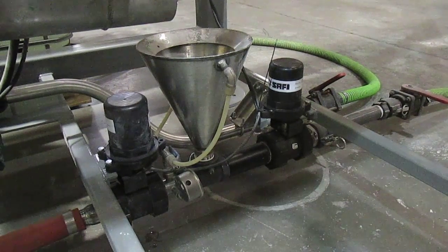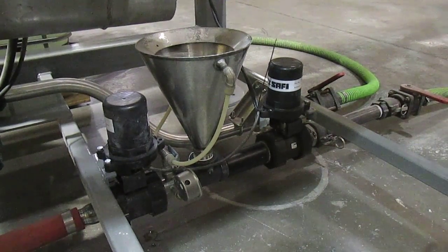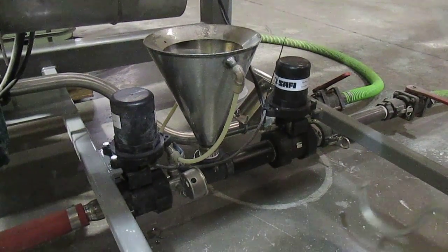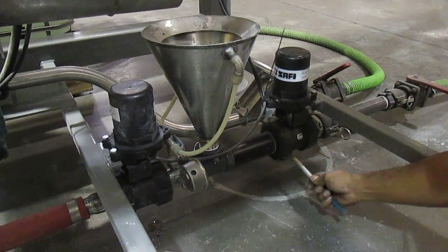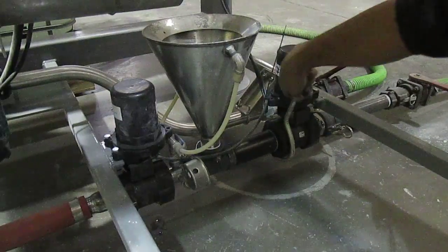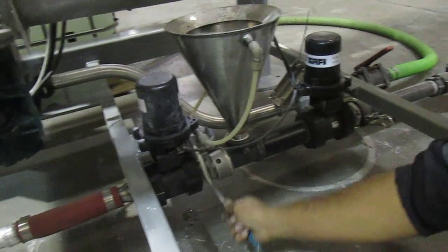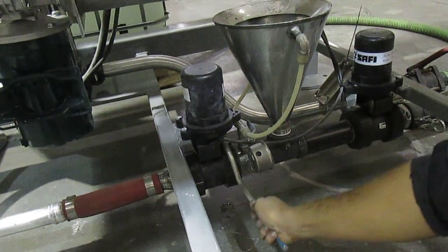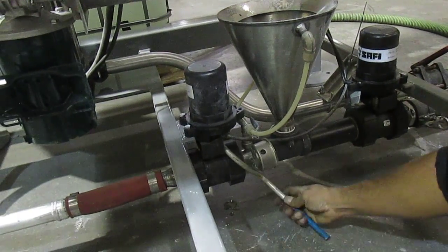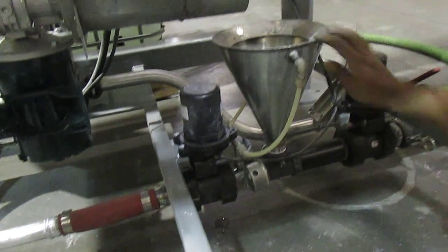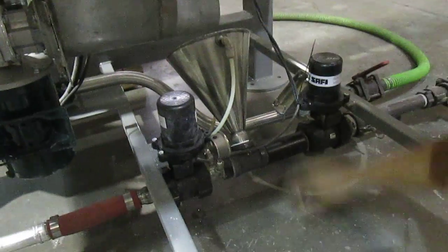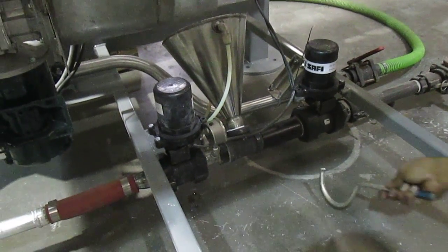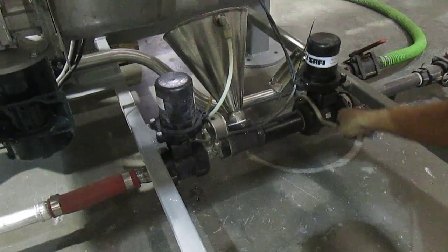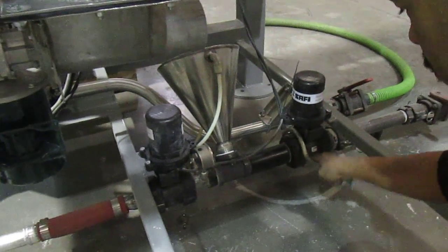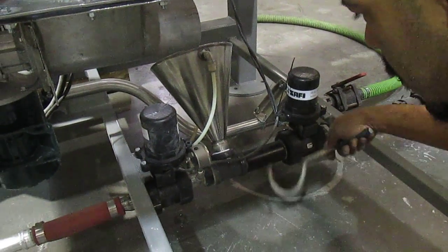First, loosen up the double union nuts on your electric ball valves, as demonstrated here. Loosen up the front ball valve, then slightly loosen the rear ball valve. Once that's done, push your cone toward the control panel, then tighten them back up snugly so that when we go into the calibration menu, you won't have any water leakage.